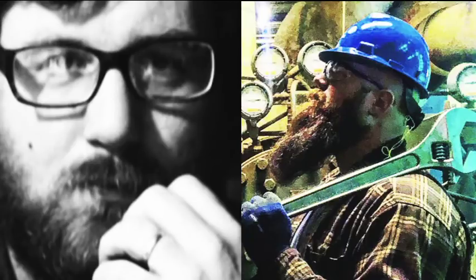So by the end of the video, we did discover that the strainer was plugged horrifically. Actually, it was probably one of the worst ones I've ever seen. As soon as we got that cleaned out and replaced, our temperature drop went back to about, at the end of the video, I think 4 degrees. So we were looking really good, and we were back at set point, which the chilled water for that building was set to 49 degrees. And we were good. So I went back the next morning. We decided not to do the full comprehensive PM, which was the plan. They had some contractors in the building doing some other work, so they didn't want the chiller offline if possible. But it was fine because the machine was running beautifully. 24 hours later, no issues. I went ahead and I left, carried on with my day.